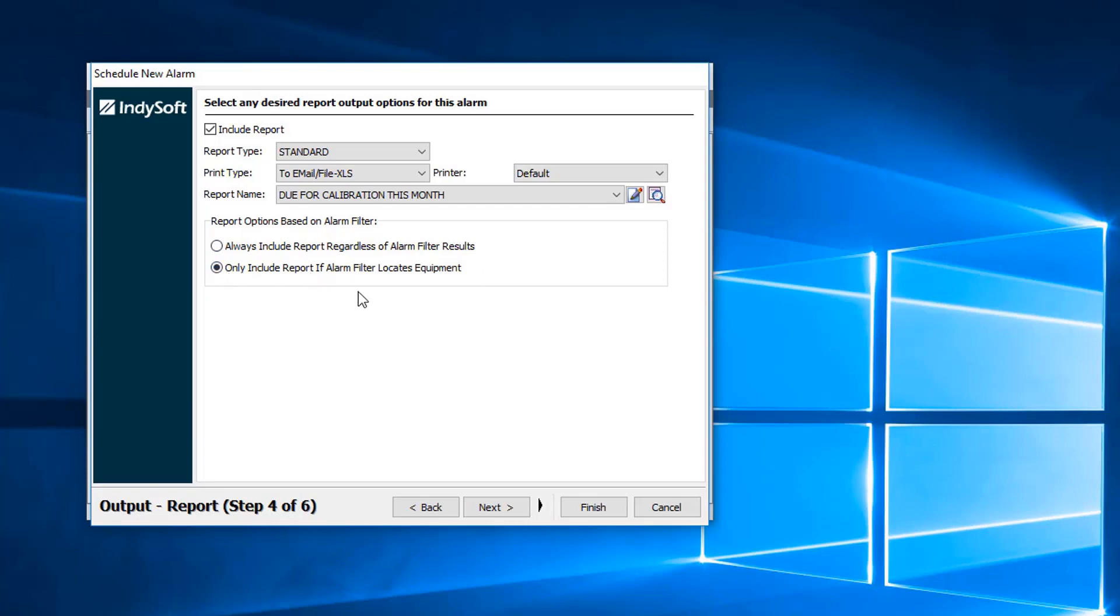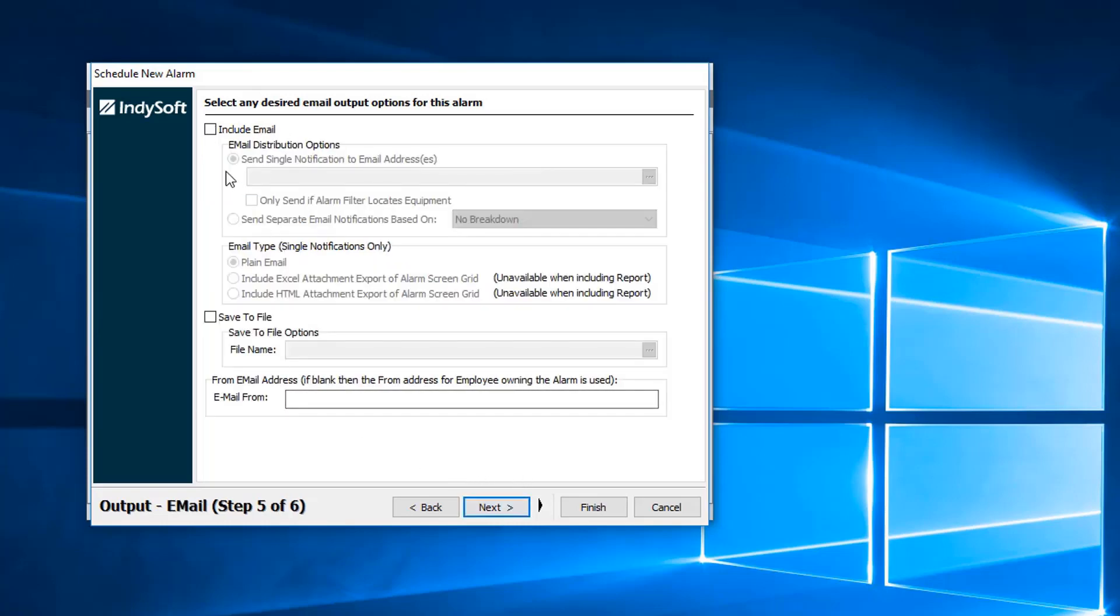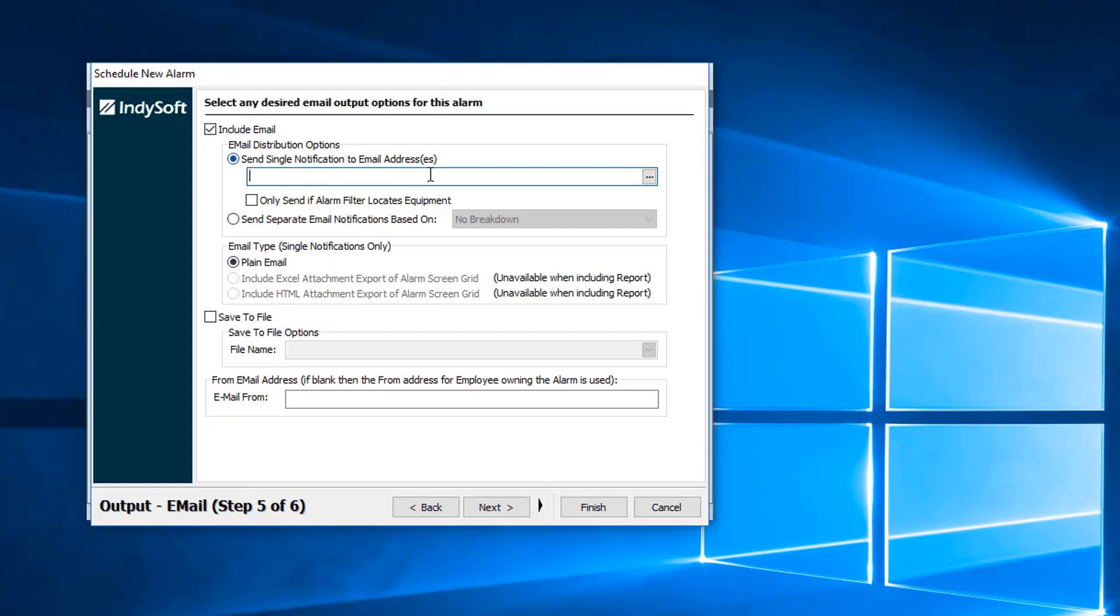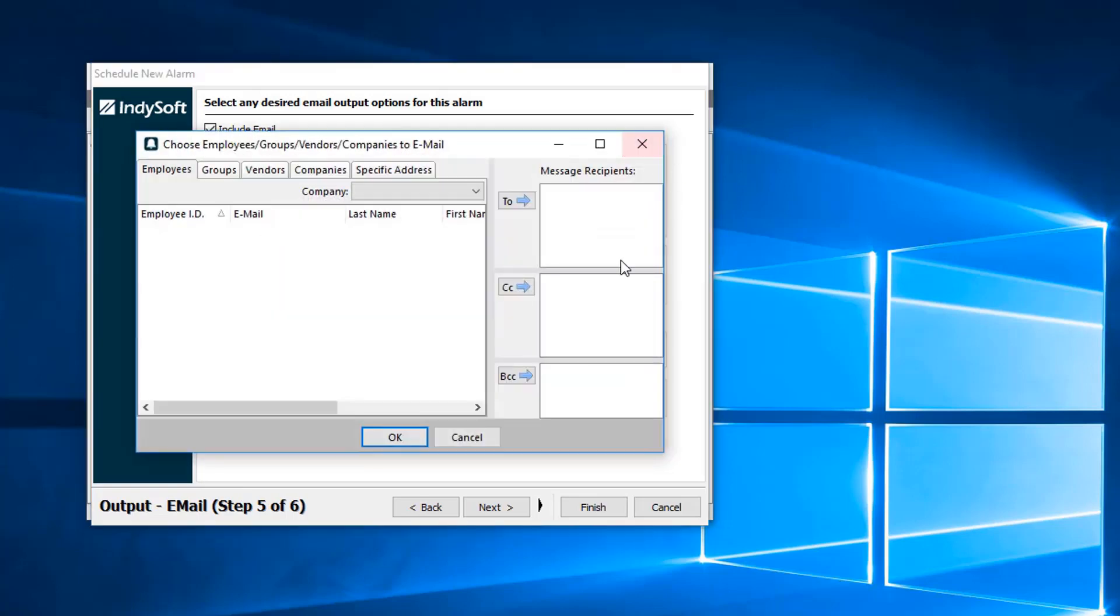You can always include the report regardless of alarm filter results, or you can only include the report if the alarm filter locates equipment. Next, we can include email addresses. This is going to be your email distribution. We can simply type in those addresses manually and add a semicolon for multiple addresses.